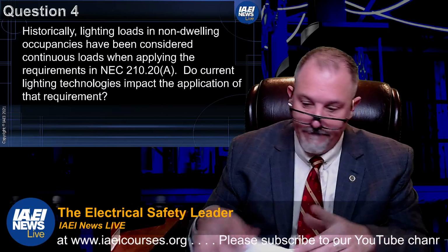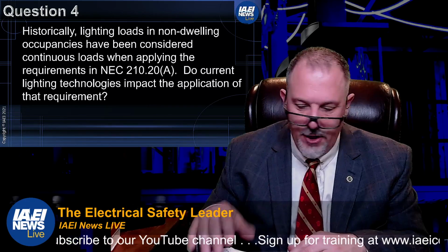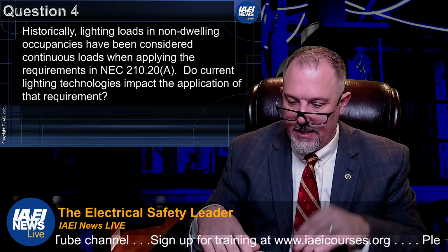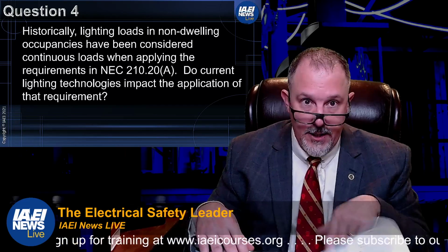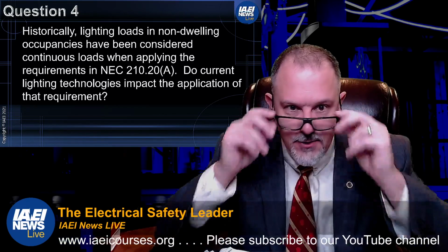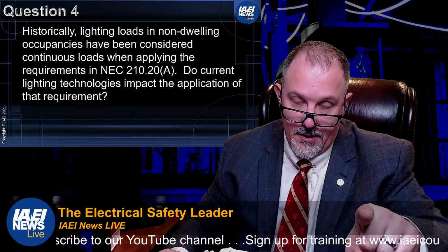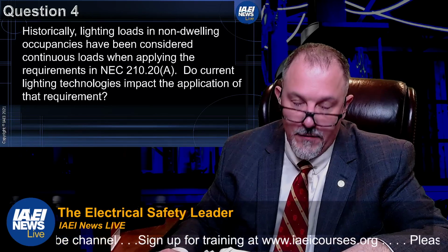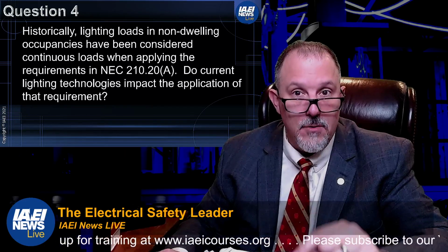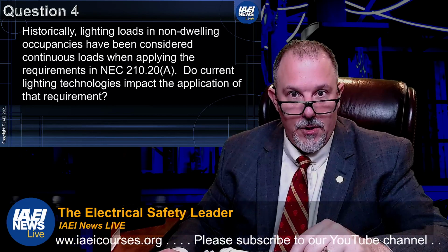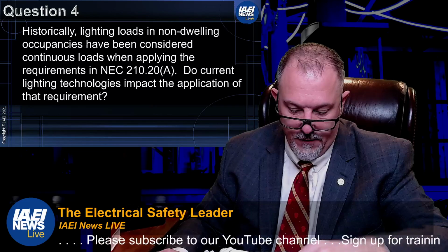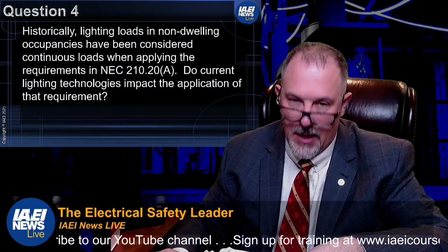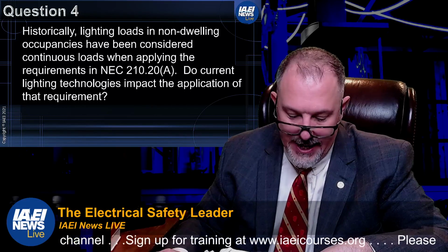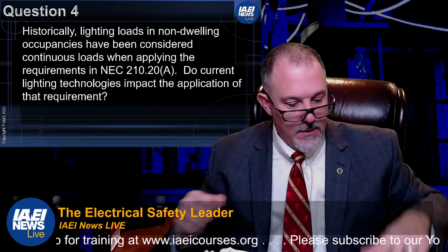Now, another complicating factor. Just when you thought you had the answer and you were going to say whatever it is you were going to say, you've got to think about all the different ramifications. And I swear I'm probably missing some. But 220.12, which is why the moment I saw 210.20 and read it, in my mind I was thinking 220.12. And the reason I bring it up is because Table 220.12 changed in the 2020 version of the National Electrical Code. We added a note to the bottom of Table 220.12 that says the 125% multiplier for a continuous load as specified in 210.20(A). Let's go to 210.20(A).